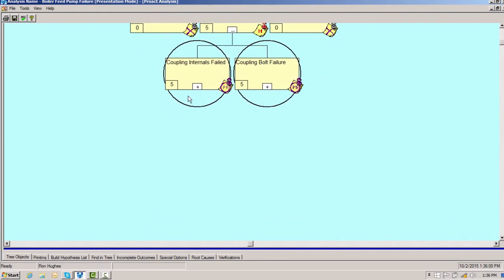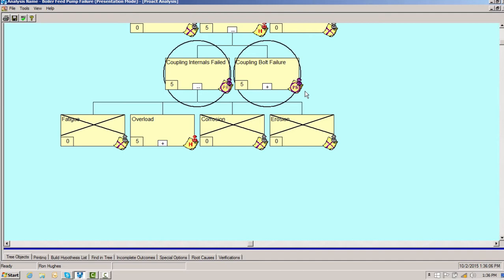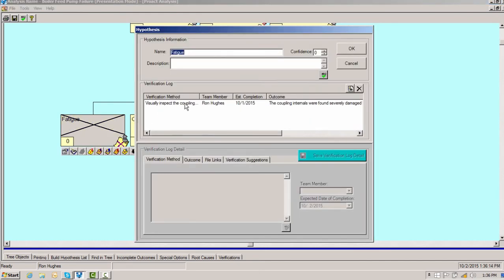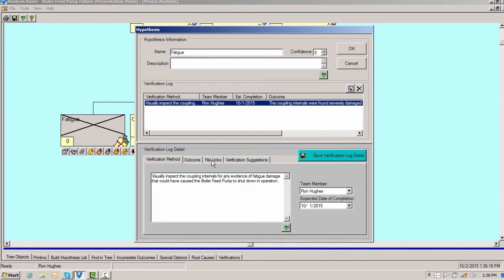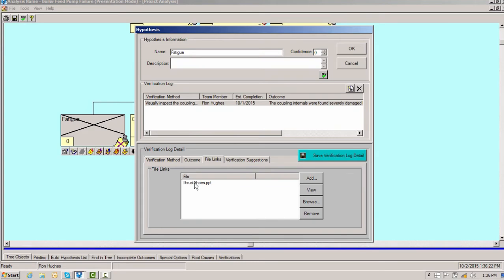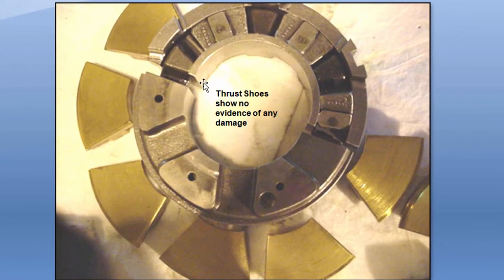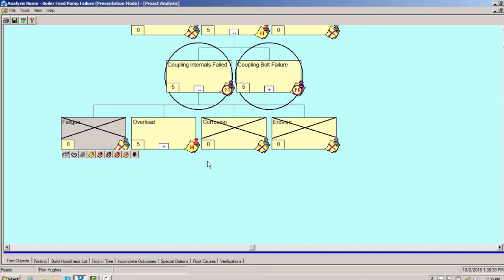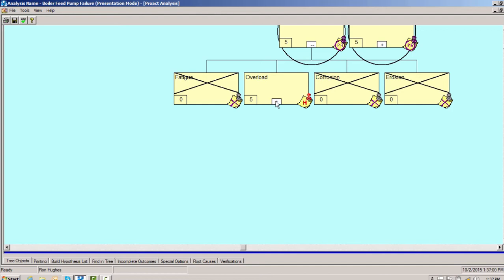How can the coupling internals fail? All components, once you get to the component level, fail for one or a combination of four reasons: erosion, corrosion, fatigue, and overload. We visually inspect the coupling internals for evidence of fatigue and can't find any. Also, if you have cyclic loading or fatigue within the equipment, it always shows up as wear on the thrust shoes — these thrust shoes show no evidence of wear, so there is no fatigue. We also look for evidence of corrosion and erosion. We see erosion on the coupling face, but on the internals themselves there is no erosion. Overload is evident by visual inspection.